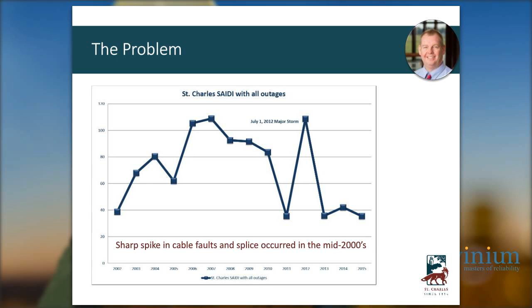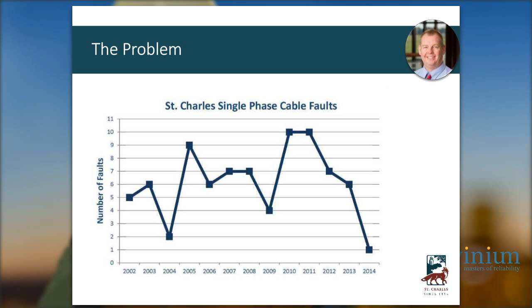The reason for the bubble we see in the mid-2000s was majority caused by some pretty major single-phase cable faults in people's backyards that led to long-duration sustained outages. Our cable faults actually got worse in 2010-11 as we were just getting into the program, but we had a sharp spike in these cable faults through the mid-2000s. We would go from 5 or 2 faults, which was pretty manageable and not very impactful to your SAIDI number, to two years in a row at 10. When you're averaging one sustained outage a month in a residential area, that obviously draws attention from your customers. The work I'm talking about here today is from our senior distribution engineer.